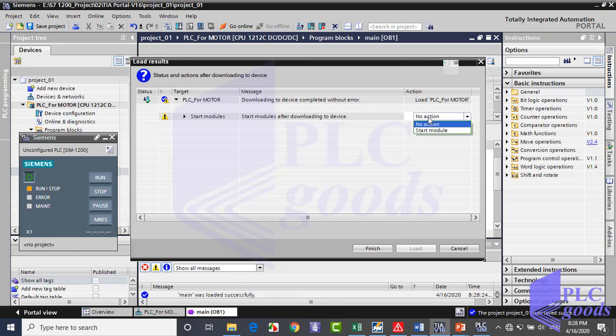There are some messages. Now click on load again. As you see, downloading is done successfully. Pay attention, there isn't any hardware switch on this SIMATIC S7-1200 CPU. To start it manually, unlike S7-300 or S7-400 CPU models. It means we need TIA software to start S7-1200 CPUs of Siemens company. So you can select start module here.